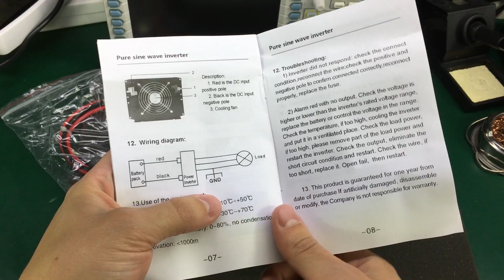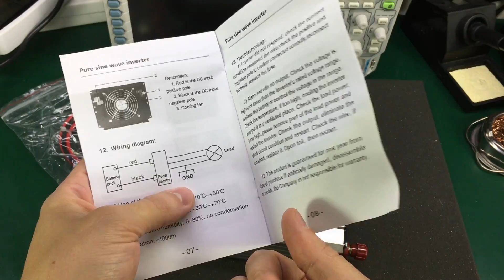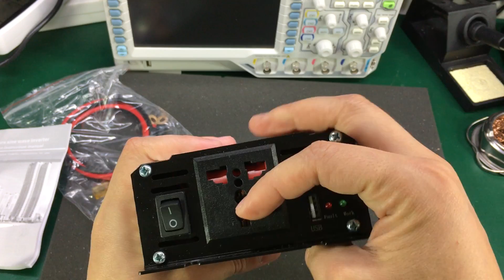By taking a quick look at the manual, you're supposed to create a common ground point on the inverter, but there is no ground point connection on the enclosure, and there is paint all around, so it will be pretty hard to get a good connection with the case to create a common ground. I guess I will run this with a floating ground.